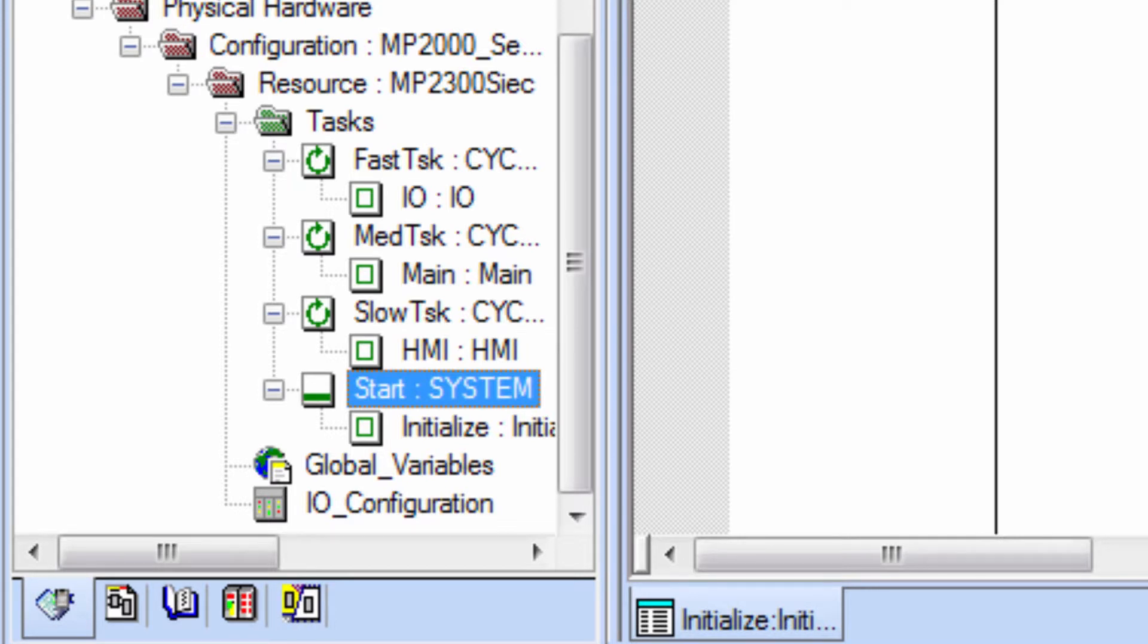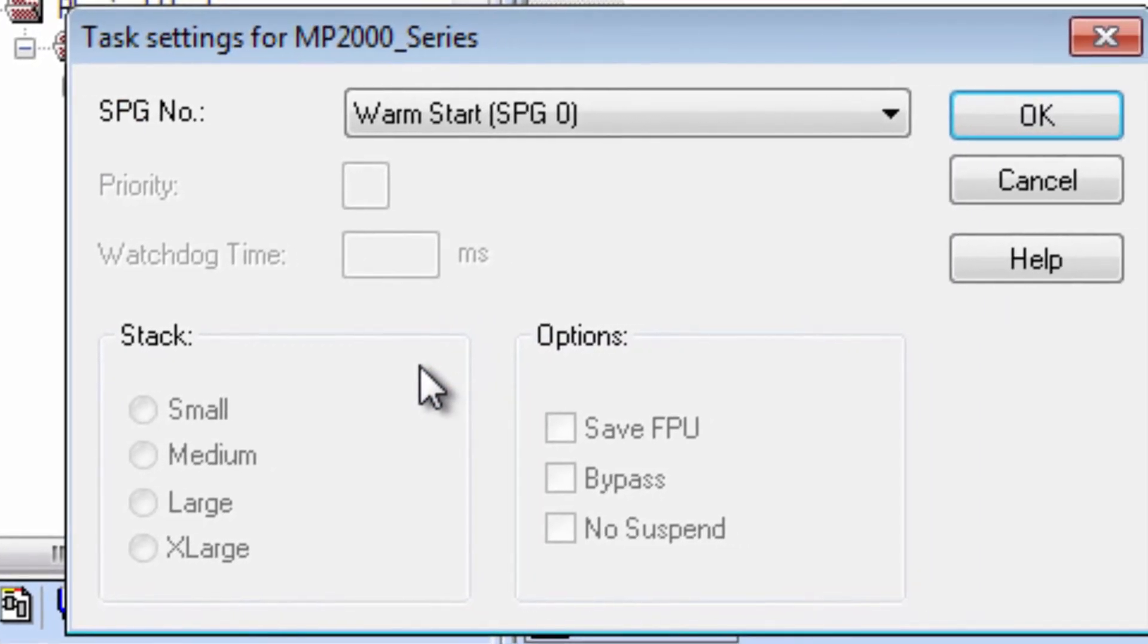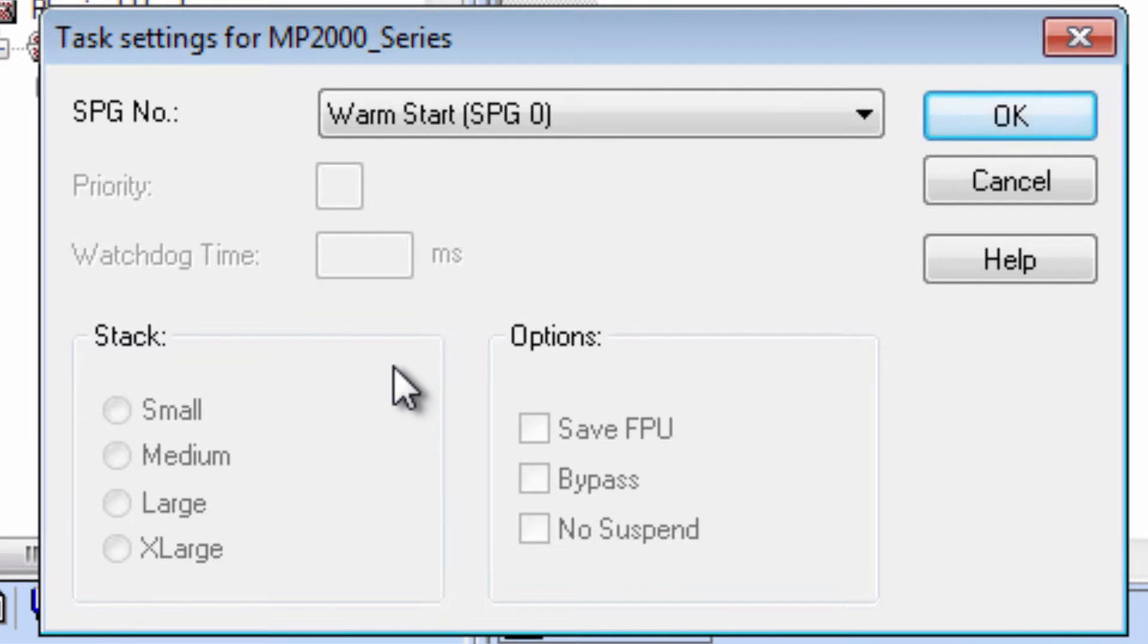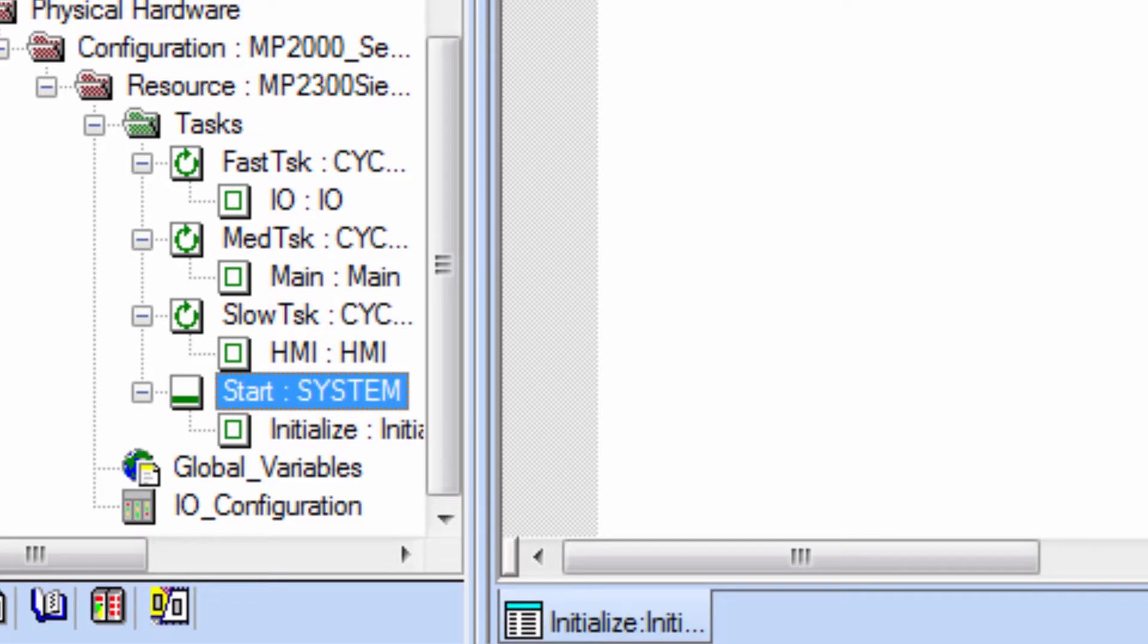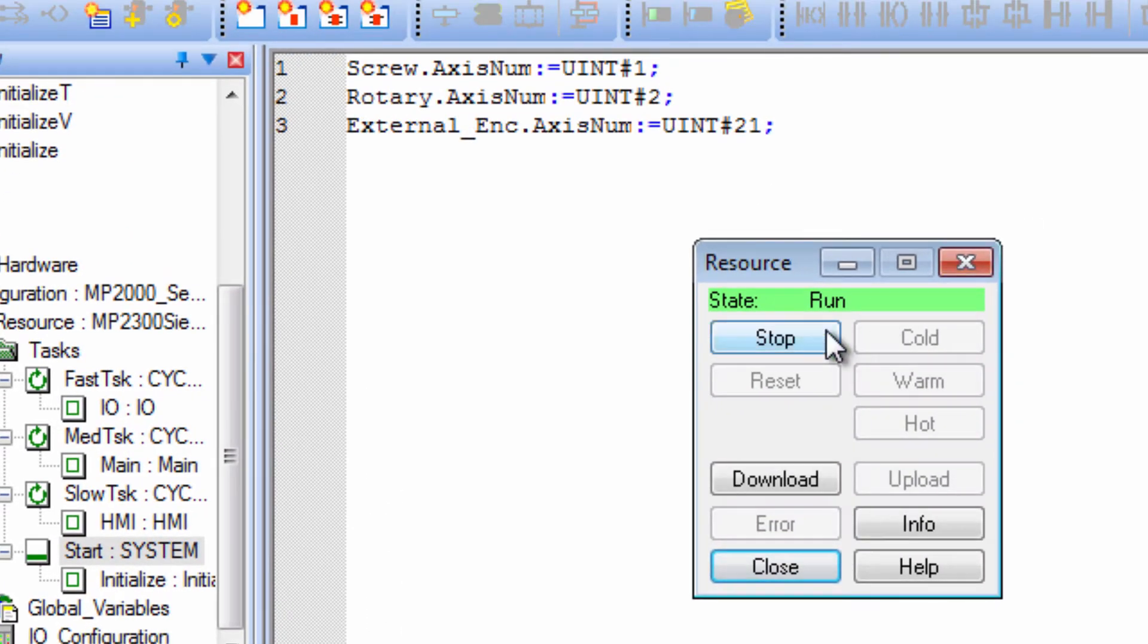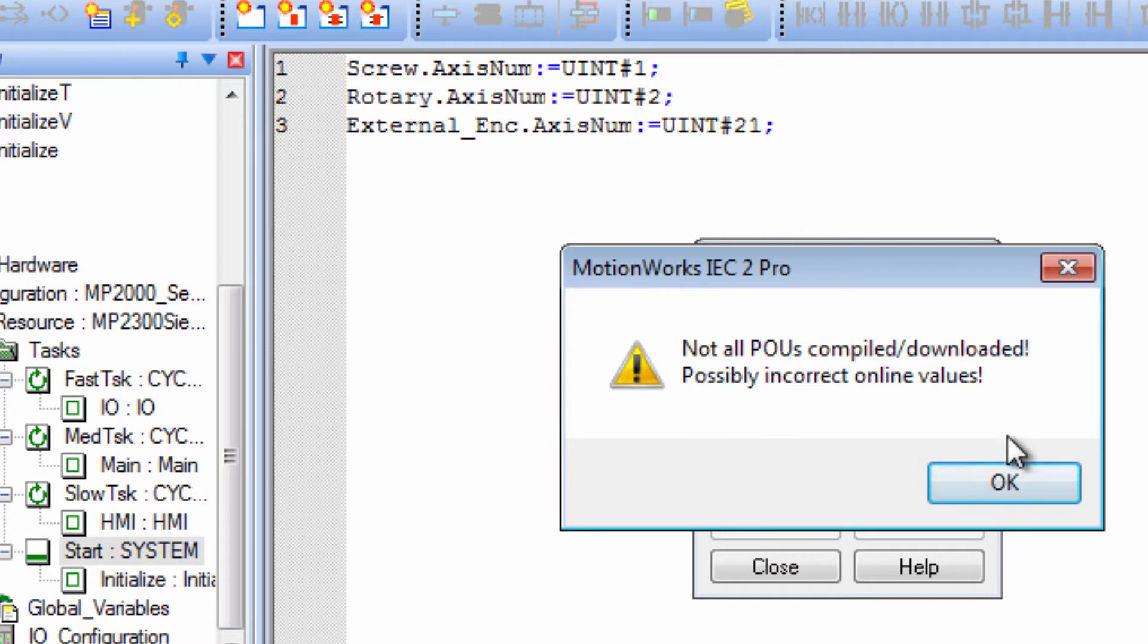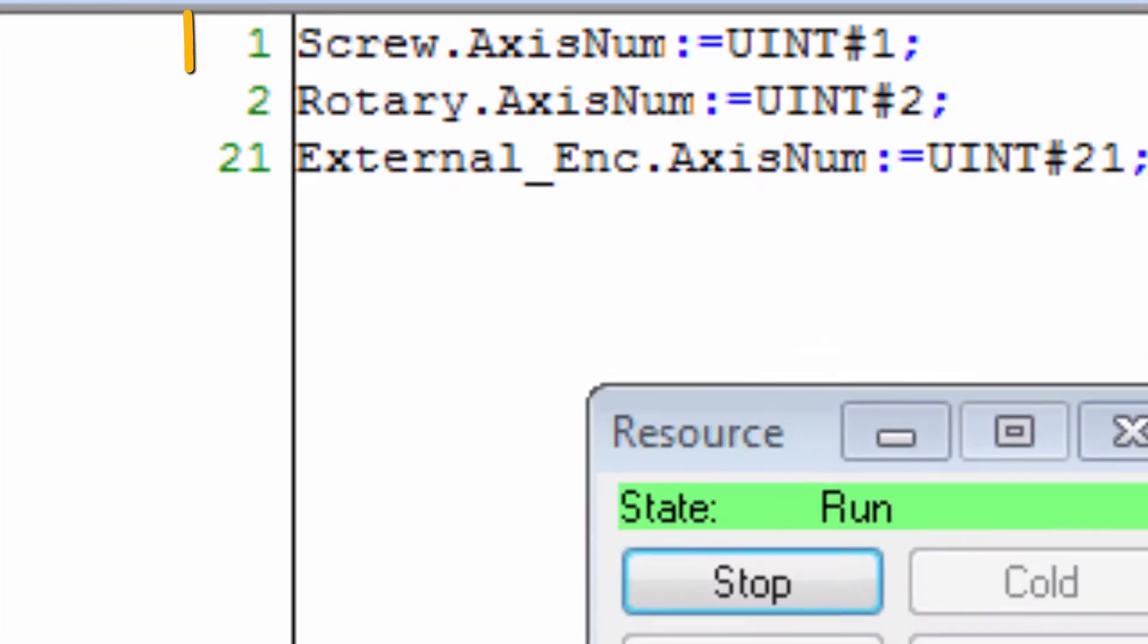Well, you can see in the task list that Initialize runs in the Start task. I'll turn off Debug Mode and right-click for the settings of this task, which shows that it will run at Warm Start, not Cold Start. Warm Start is the equivalent of Power On. I did Cold Start, which is the equivalent of a first-time machine startup. I'll stop and Warm Start. Now in Debug, you see the values loaded.